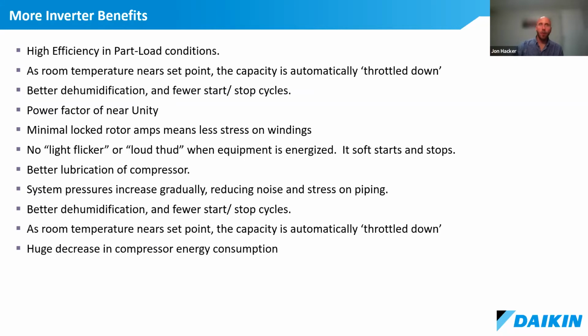So there's a number of benefits that are provided by inverters. I think we covered a lot of them. I think the reality is, just to summarize, inverters allow the equipment to operate at higher efficiency in part load conditions and thus provide better seasonal performance. And they do a better job of maintaining comfort by throttling the system down as it approaches its set point.